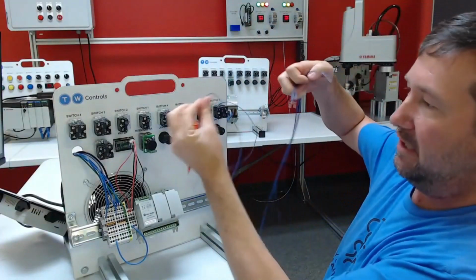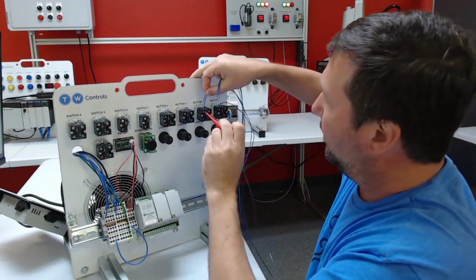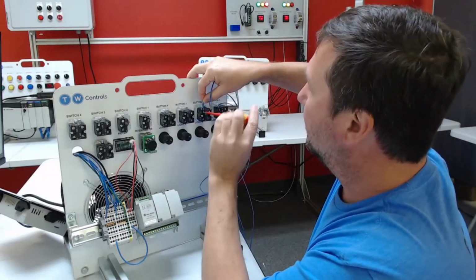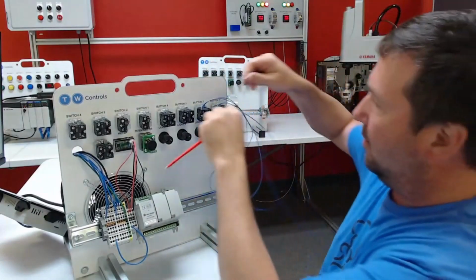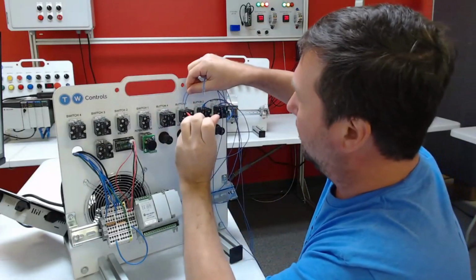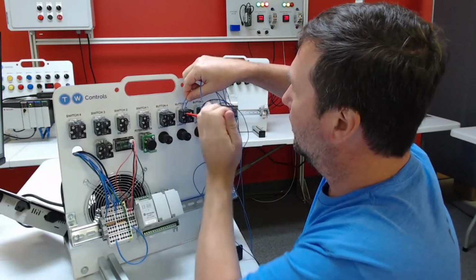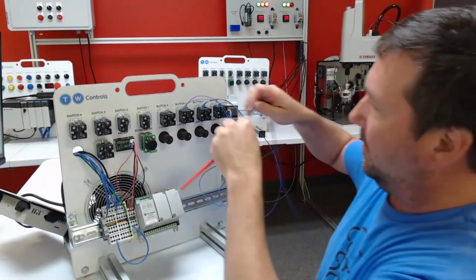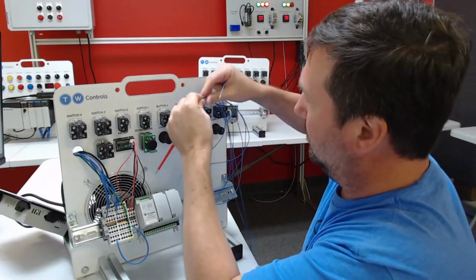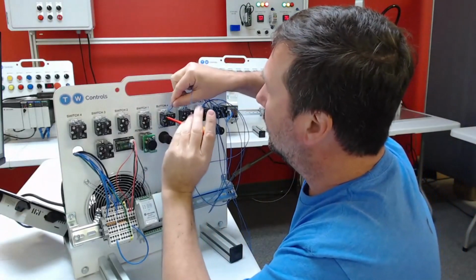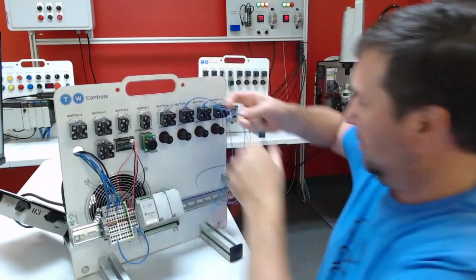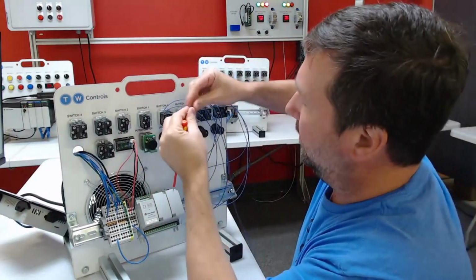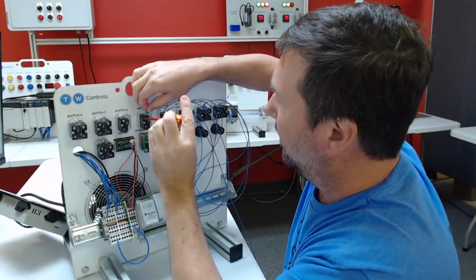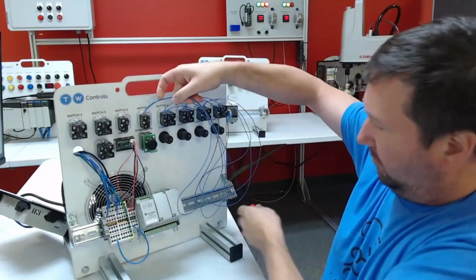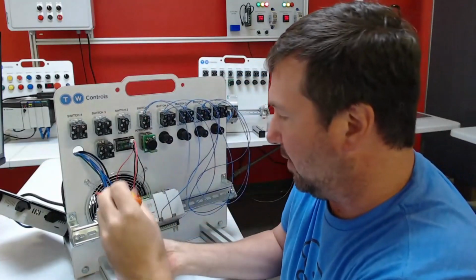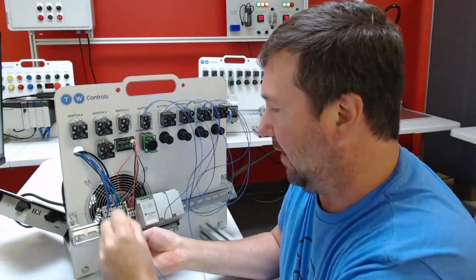So I have one wire in the first one, and I'll take that wire and another wire, and I'll put it into button 2. And then I'll take that wire and another wire and put it in button 3. And then I'll take that wire and another wire and put it in button 4. And then I'll take that wire and an additional wire and put it into switch 1. So that is going to jumper all of these, and I'm going to connect this to our plus 24 volt. And that'll be any of the left terminals right here.